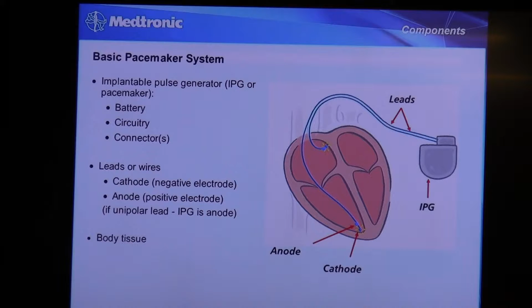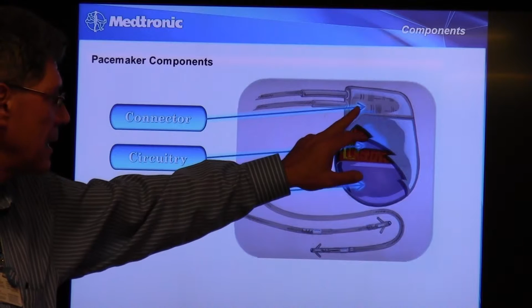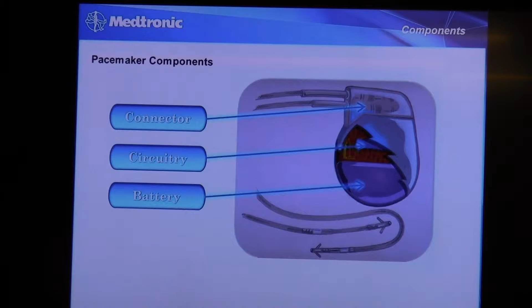And this actual pacemaker has logic circuitry in it that will analyze: did the heartbeat happen? If it happened, what's the timing cycle that we talked about? That's the battery of the pacemaker. Nowadays it lasts anywhere from 6 to 8 years, 9 years, even longer than that sometimes, depending on how it's used. And that's the connector, which you guys can pass around. You can see there's a receptacle and a connector.